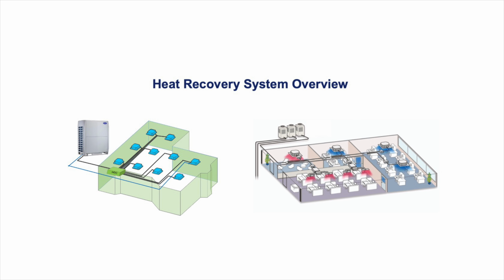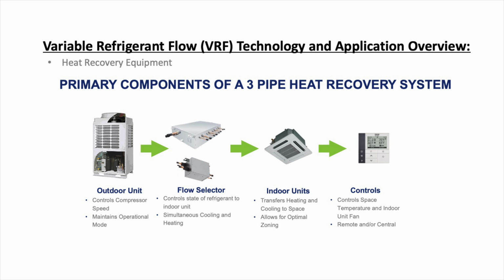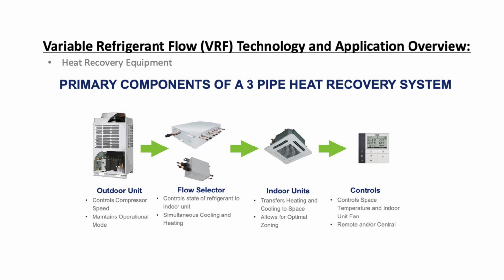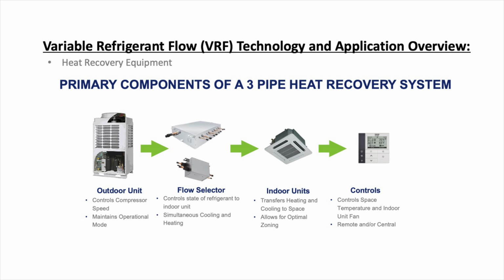Now let's look at a heat recovery system. The primary components of a heat recovery system are similar to a heat pump, but on a heat recovery system, you have a flow selector box or a branch selector or a heat recovery box. This is what controls the state of the refrigerant to the indoor unit, and this is what allows for simultaneous heating and cooling in a heat recovery system. And again, you have the other components as well: the outdoor unit, the indoor unit, and the controls.